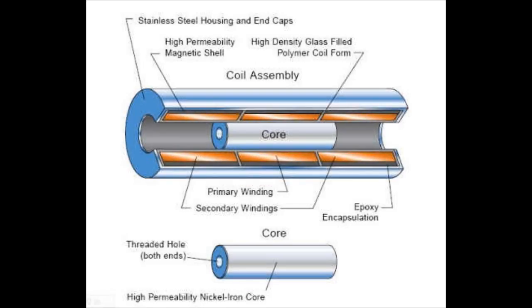The figure shows the components of a typical LVDT. The transformer's internal structure consists of a primary winding. This primary winding is centered between a pair of identically wound secondary windings. These secondary windings are symmetrically spaced about the primary. The coils are wound on a one-piece hollow form of thermally stable glass-reinforced polymer, encapsulated against moisture, wrapped in a high permeability magnetic shield, and then secured in a cylindrical stainless steel housing. This coil assembly is usually the stationary element of the position sensor.